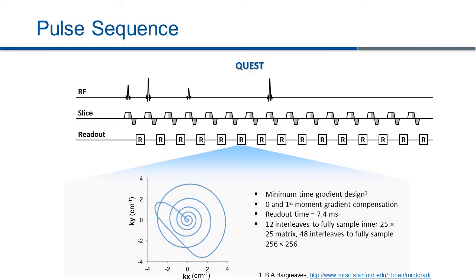We implemented this 4-RF QUEST block in a Siemens scanner. For this QUEST sequence, we used conventional unbalanced slice selection gradients to achieve the dephasing moment between the RF pulses, and we used spiral trajectories to acquire these high-order echoes. The spiral readout gradients are 0th and 1st moment compensated. The readout time is 7.4 milliseconds. For this particular study, the spiral requires 12 interleaves to fully sample the inner 25×25 matrix and 48 interleaves to fully sample the 256×256 matrix size.